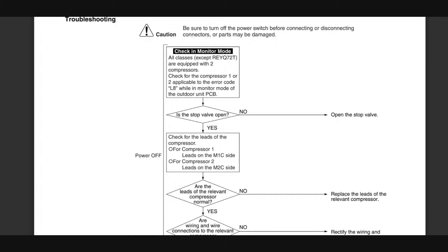Take the alarm, follow the chart. Whatever the alarm says, even at the thermostat. So a lot of the times the alarms at the thermostats won't tell you what the alarm at the condenser is. Sometimes they will, or the outdoor unit. But they will lead you to check the outdoor unit. And so you'll have to take that alarm from the indoor, go to the outdoor, and then see what the code at the outdoor is, and then begin your troubleshooting from there.